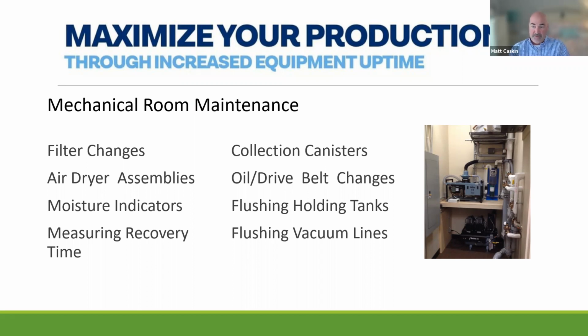And we like to measure that recovery time. It's typically a minute and a half or whatever it is for that pump up time. And we can tell a lot from the performance of your air compressor. If that time starts to extend out, that's usually an indication that you've got something going on in the office, whether it be an air leak, or you've got some moisture in the tank and the compressor is having to work harder and that sort of thing. So we like to check that as well.